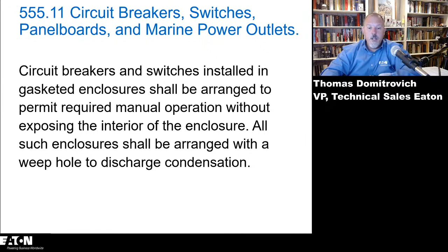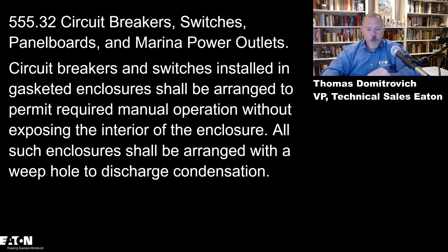Circuit breakers and switches installed in gasketed enclosures shall be arranged to permit required manual operation without exposing the interior of the enclosure. Again, arranged with a weep hole to discharge condensation. Right? So there's special requirements for circuit breakers, switches, panelboards, and marina power outlets. All such enclosures shall be arranged with the weep holes.